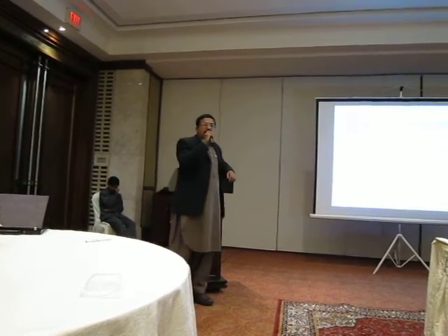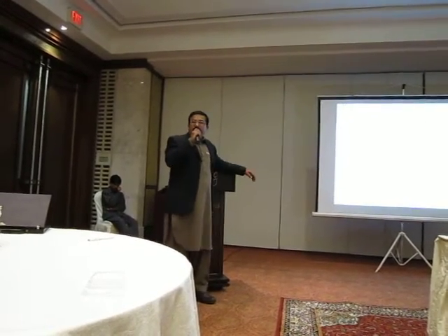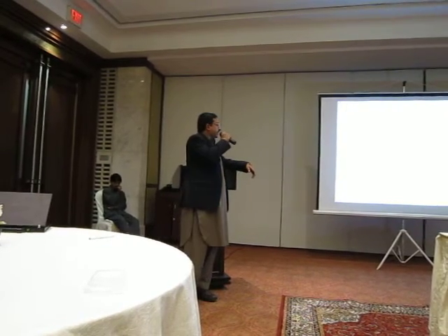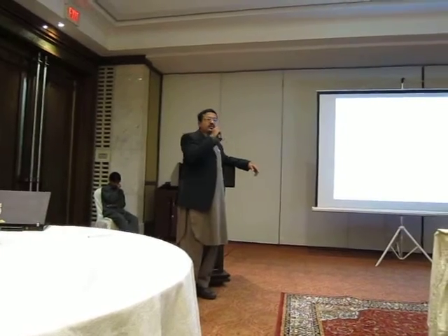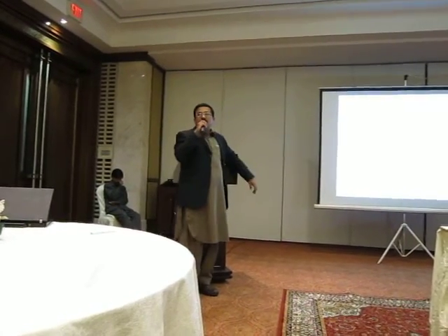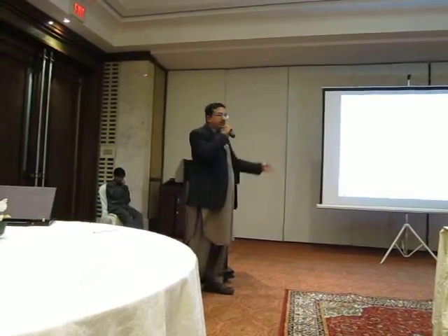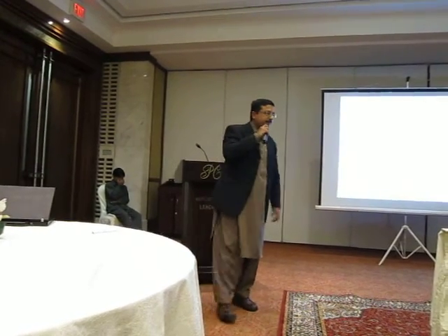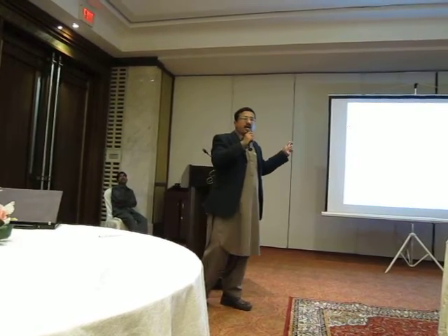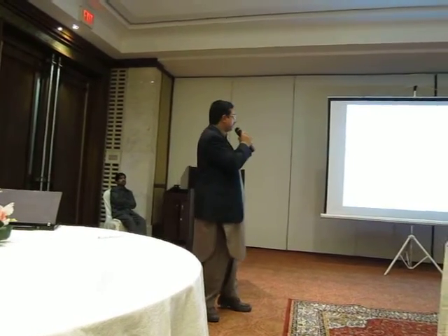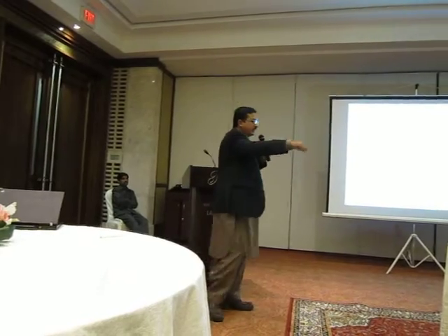Bacterial removal efficiency after the formation of the biolayer is 92 to 96%. It is 100% effective in parasite removal, and it also helps to improve taste and odor. Basically, I have given you the theory of how slow sand filters work. Now I give you a graphical representation of how the inside of the filter works.